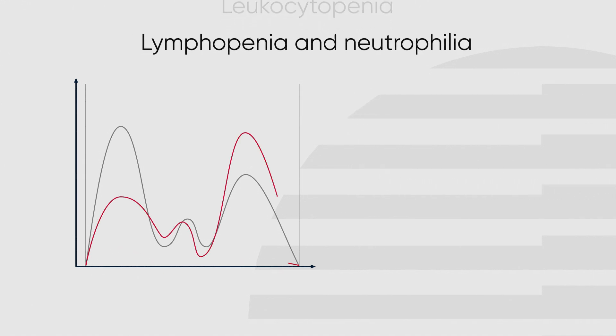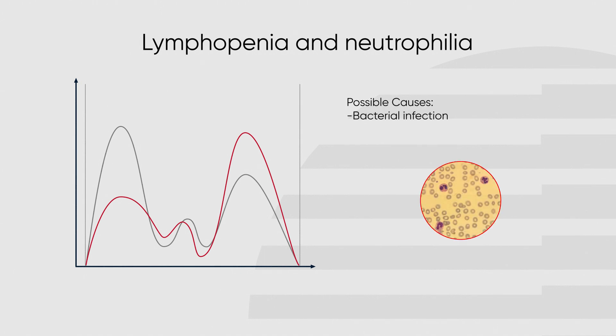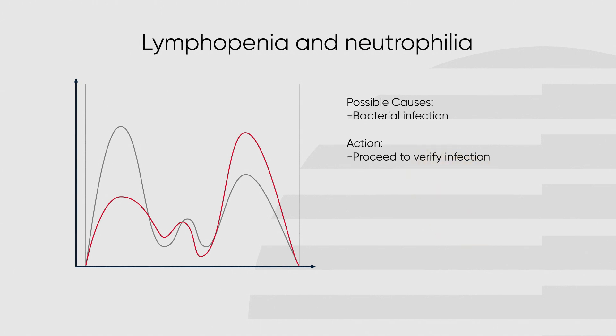A decrease in the lymphocyte peak combined with an increase in the granulocyte peak is an indication of a bacterial infection, such as E. coli. If this occurs, proceed to verify infection.